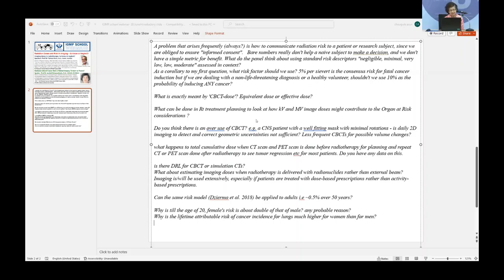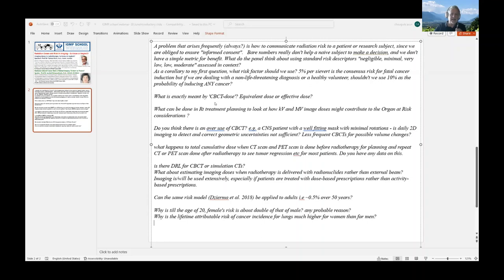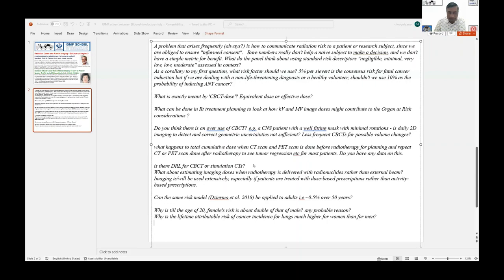A short question to Thomas Krohn: what exactly is meant by CBCT dose — equivalent dose or effective dose? That is an excellent question. It depends. We typically quote equivalent dose because that is familiar to radiation oncologists who are interested in dose to critical structures — such as the equivalent dose to the rectum or bladder. However, if we are talking about risk for the patient, for example in a clinical trial, we use effective dose. Both units are used, and it is important for the radiotherapy physicist to specify exactly what they are quantifying.